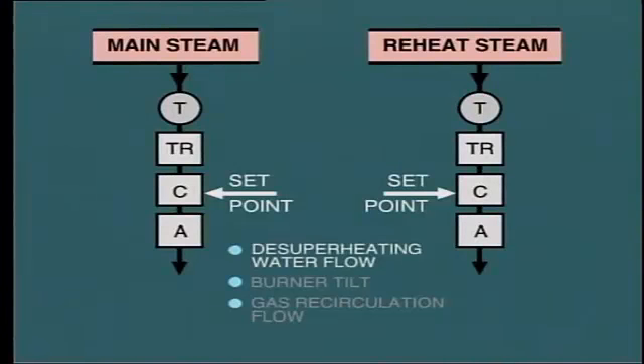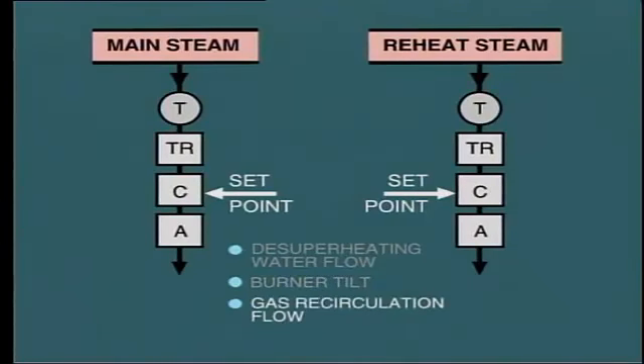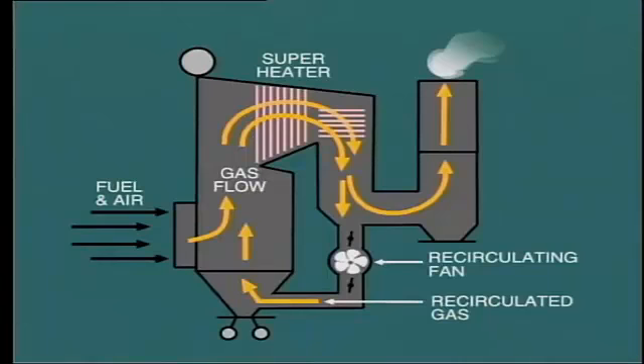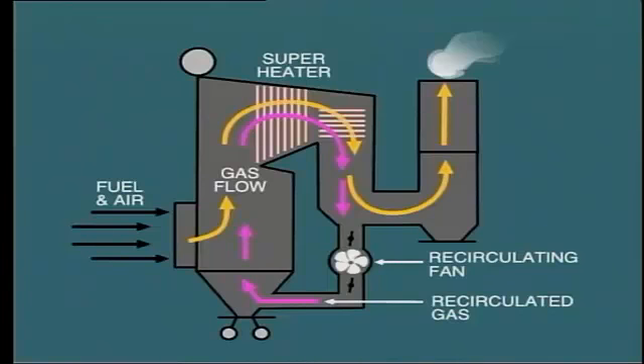Steam temperature control is also independent of the combustion control system. Final and reheat steam temperatures are measured and processed through a controller to actuate one or more attempering devices, such as adjusting the flow of de-superheating water, adjusting the tilt of the burners, or adjusting the flow of gas recirculation. This last technique provides the same effect as firing with increased excess air but without the increased heat loss up the chimney. The recirculating gas merely circulates in a closed loop while increasing the mass of gas flow across the superheater tubes, with consequent increase in main steam and reheat temperatures.